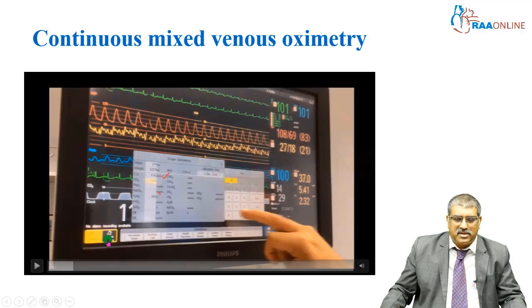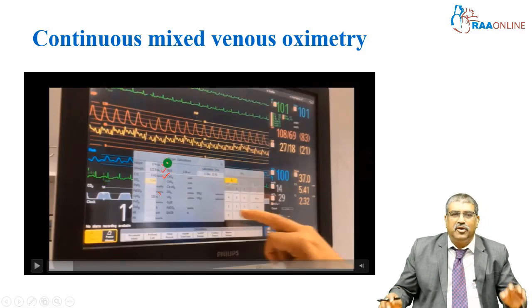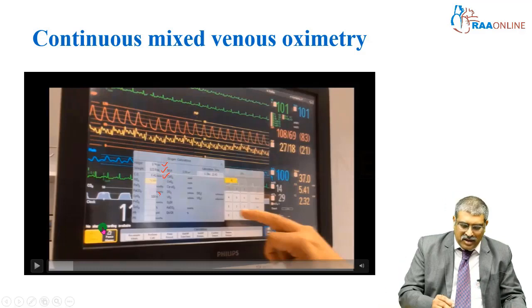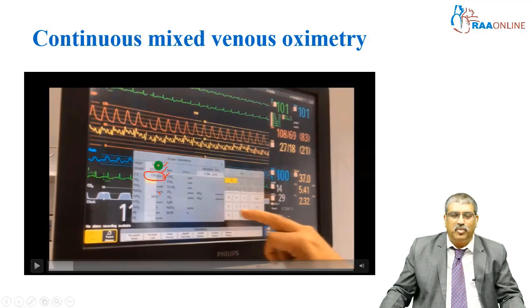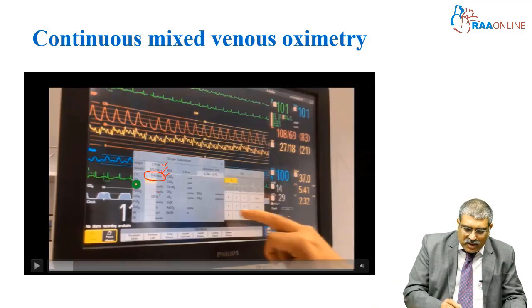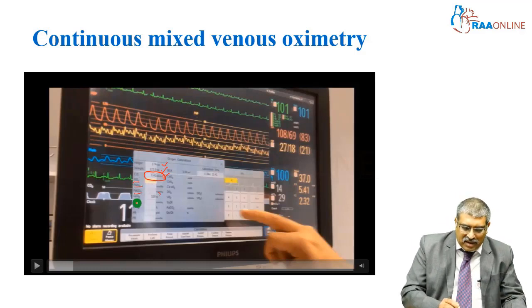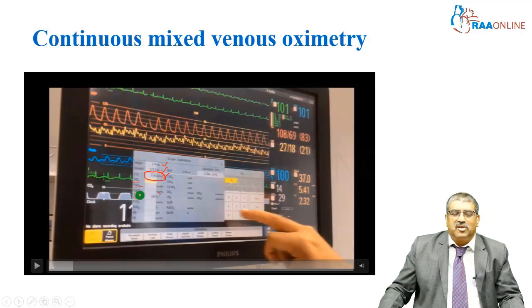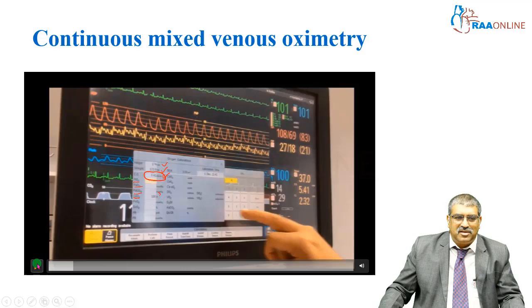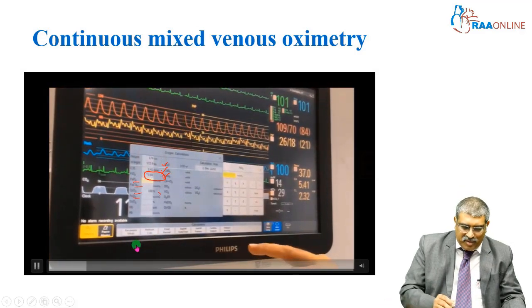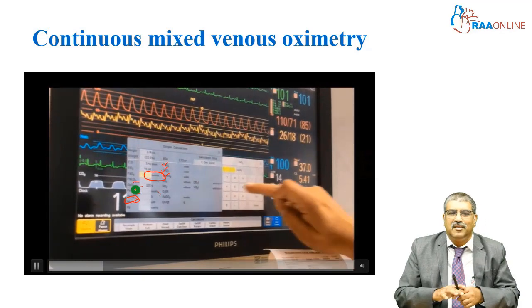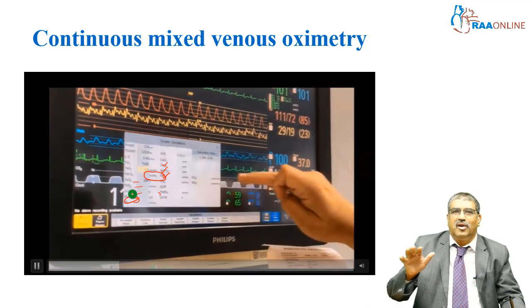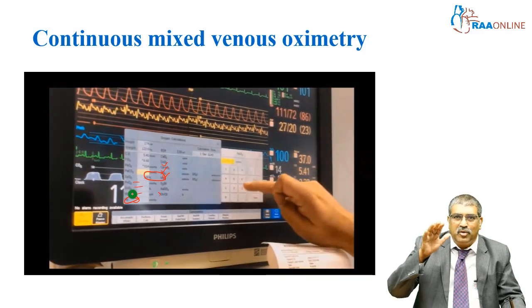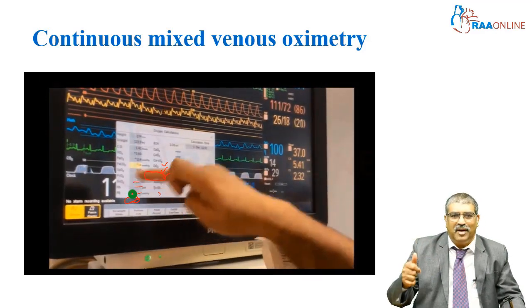Here while in calibration, you enter the height and weight and you get the body surface area. Once you enter the value, you get the cardiac output after entering the other variables. But with regard to oxygenation, you enter the FiO2, PaO2, PCO2 which is obtained from the ABG, and from the pulse oximeter you record your arterial oxygen saturation. As you enter all the variables, you get the SvO2, which is the mixed venous oxygen saturation. For this you have to enter all the variables and you have to calibrate, and then you get the value.